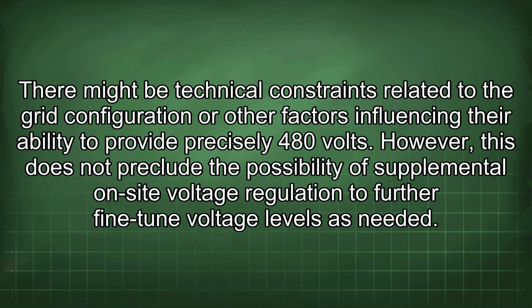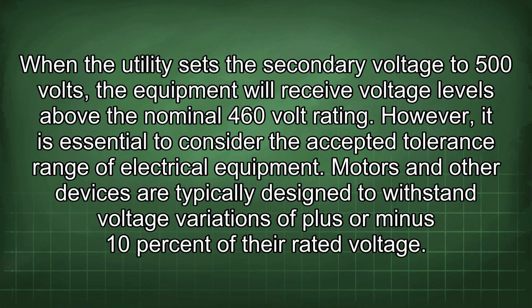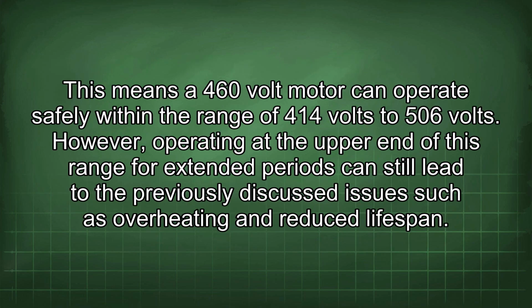However, this does not preclude the possibility of supplemental on-site voltage regulation to further fine-tune voltage levels as needed. When the utility sets the secondary voltage to 500 volts, the equipment will receive voltage levels above the nominal 460 volt rating. However, it is essential to consider the accepted tolerance range of electrical equipment. Motors and other devices are typically designed to withstand voltage variations of plus or minus 10% of their rated voltage. This means a 460-volt motor can operate safely within the range of 414 volts to 506 volts.